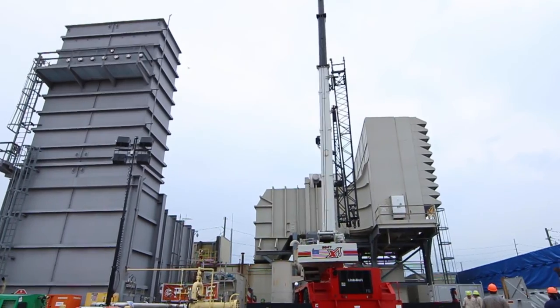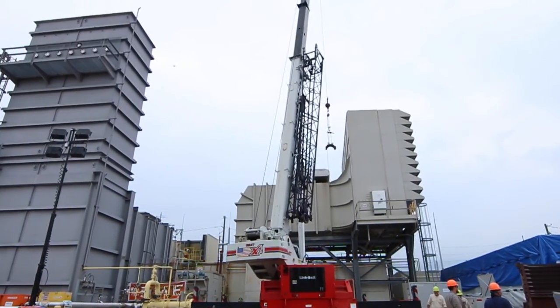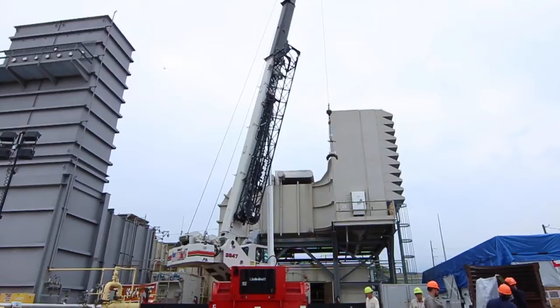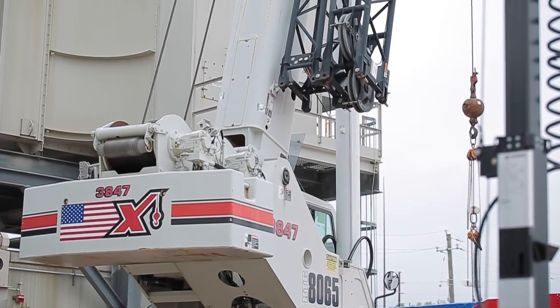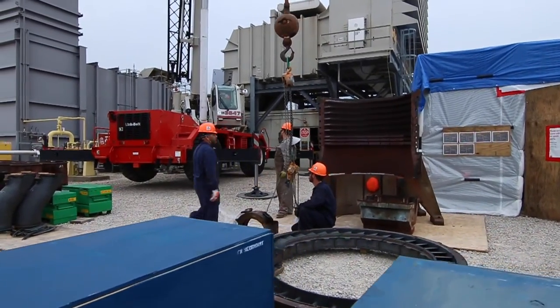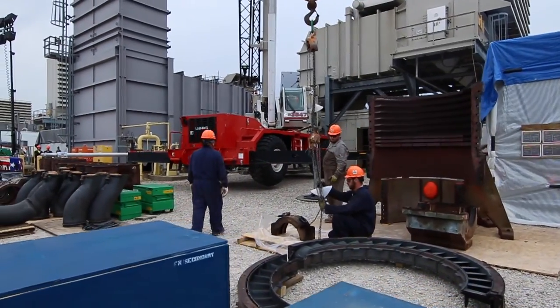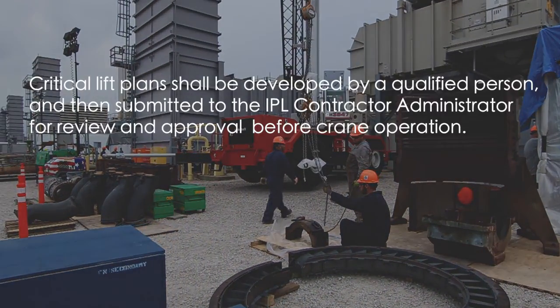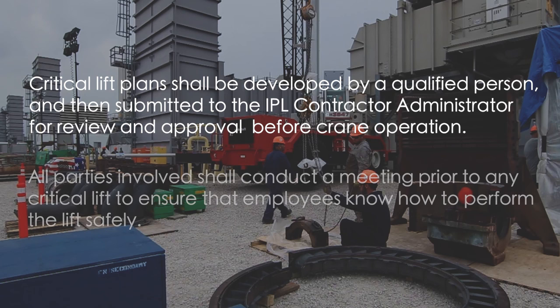If the voltage is unknown, minimum required clearance is 20 feet. You shall follow applicable OSHA regulations and manufacturer's instructions for crane operations, including but not limited to, critical lift plans shall be developed by a qualified person and then submitted to the IPL Contractor Administrator for review and approval before crane operation. All parties involved shall conduct a meeting prior to any critical lift to ensure that employees know how to perform the lift safely.